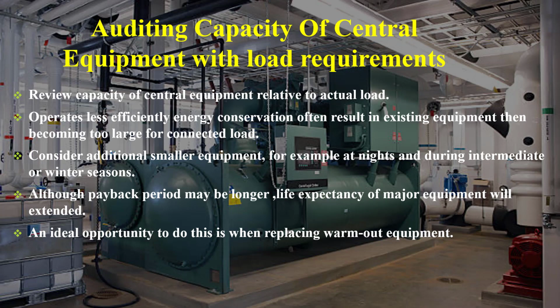Auditing capacity of central equipment against load requirements. Review capacity of central equipment relative to actual load. Oversized equipment operates less efficiently. Energy conservation often results in existing equipment then becoming too large for the connected load. Consider additional smaller equipment, for example for nights and during intermediate or winter seasons. Although the payback period may be longer, the life expectancy of major equipment will be extended. An ideal opportunity to do this is when replacing worn-out equipment.